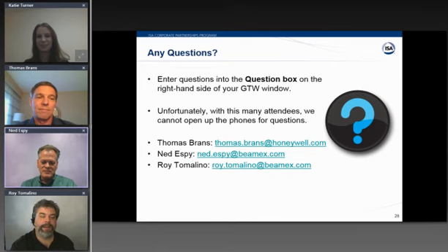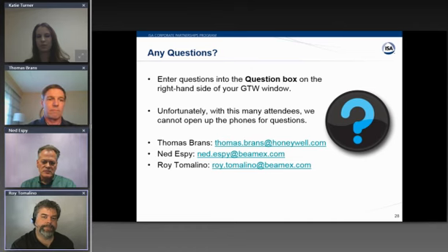You got to do them one channel at a time. I think the thing that Roy showed on the video with our colleague Mike, that fieldbus transmitter multiplexes, but when you're calibrating, you're stepping through each channel one at a time. So you do your data acquisition or recording of readings fixed on a channel. Then once you've recorded, you can move to the next channel and so on. So there's got to be a way to step through it to be able to calibrate it. That's true.